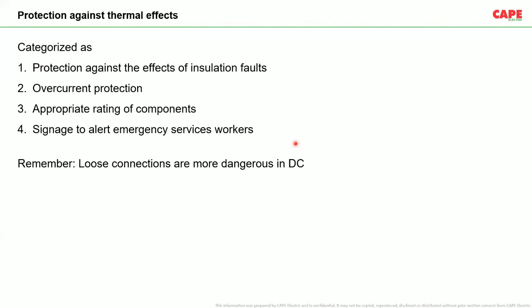Number two, overcurrent protection. Of course, you must understand that overcurrent protective devices are not very efficient, but special fuses are available which are able to disconnect at a current a little bit higher than the nominal current. But please understand that it takes a lot of time. That means the electrical installation, the wiring, and the accessories must be able to withstand that particular time.